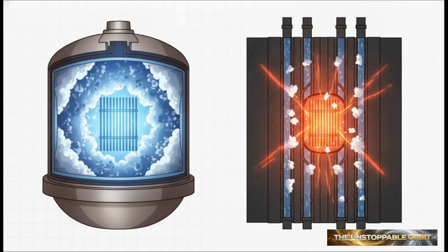This right here is where we see a massive engineering divide between different reactor types. In light water reactors, the water is playing double duty. It's both the coolant and the moderator. So, if it gets so incredibly hot that it boils into steam voids, well, you lose your moderation entirely. The chain reaction simply stops. The void coefficient is safely negative.